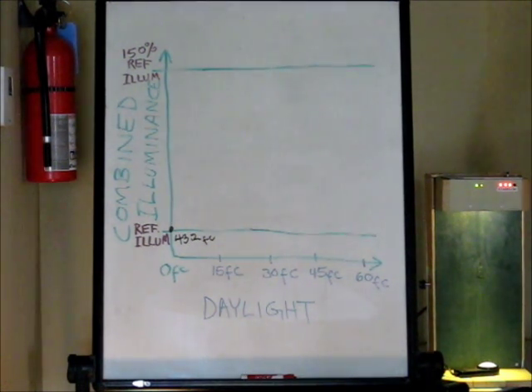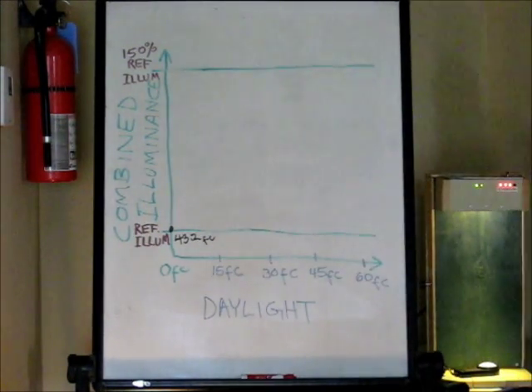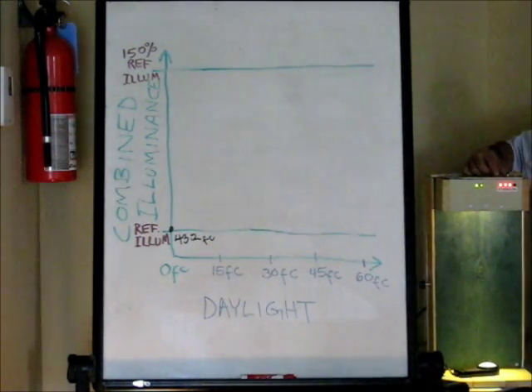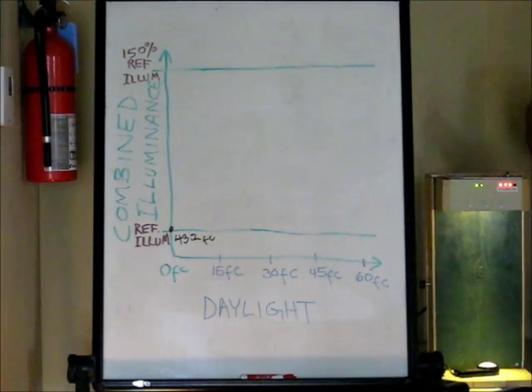They want to ensure that the lowest lighting levels in the room, which is when a stage just snaps off, is keeping you above your reference illumination. Just like with a continuous case, we don't want to drop below the genuine 3 in the morning, no daylight electric level. So I'm reading 52.7. And I'm going to make an extra step and flip off the area controls and see what kind of daylight I've got. I'm at 20 foot candles daylight.